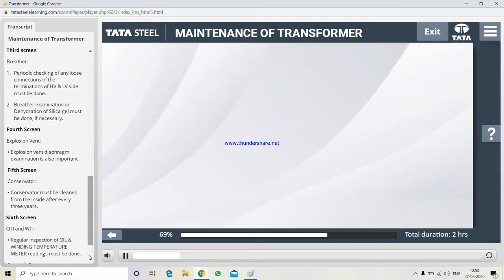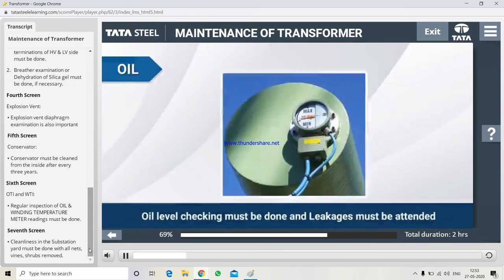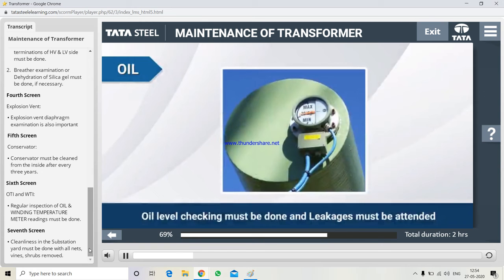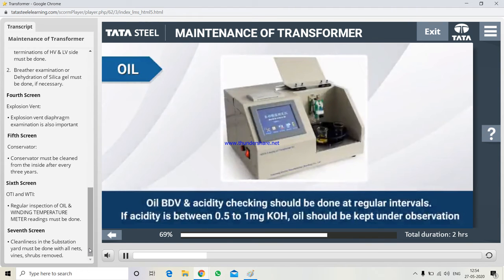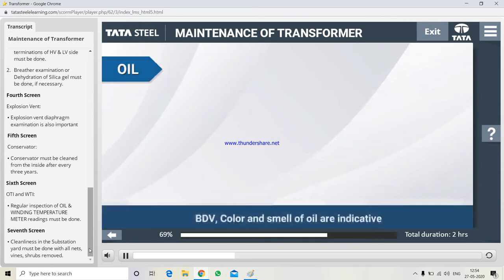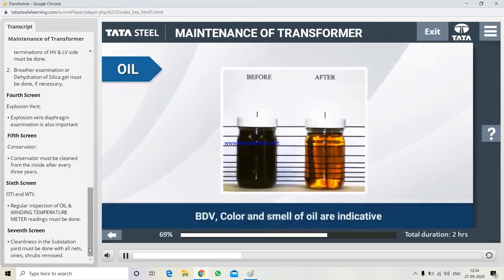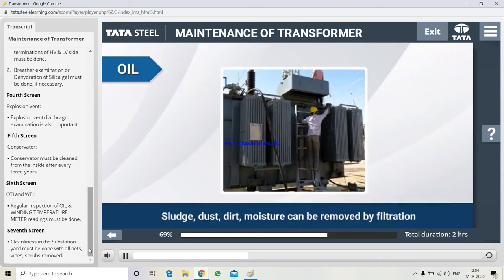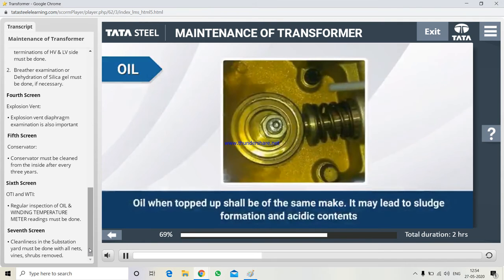First, oil. 1. Oil level checking must be done and leakages must be attended. 2. Oil BDV and acidity checking should be done at regular intervals. If acidity is between 0.5 to 1 mg KOH, oil should be kept under observation. 3. PDV, color and smell of oil are indicators. 4. Sludge, dust, dirt, moisture can be removed by filtration. 5. Oil when topped up shall be of the same make. It may lead to sludge formation and acidic contents.